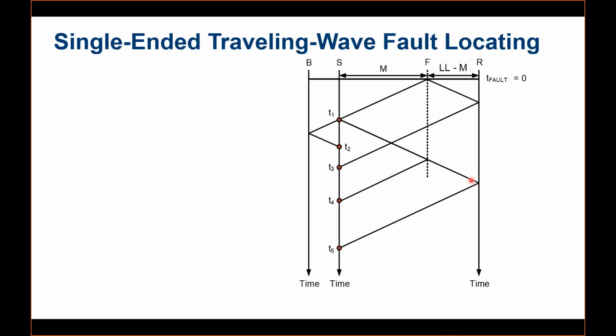This is still better than the impedance-based method, and how it works is pretty simple. Whenever you have a fault on a line at the point M along the line, it will launch traveling waves. The traveling waves will travel to point S, and they will also travel to point R. Because we don't have any communication with the remote relay, we cannot take information from the remote end, so we just have to rely on the local traveling waves.